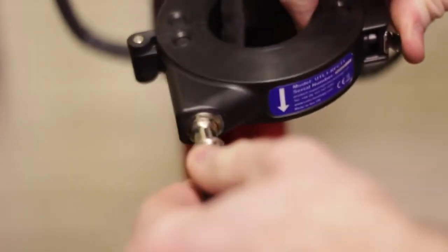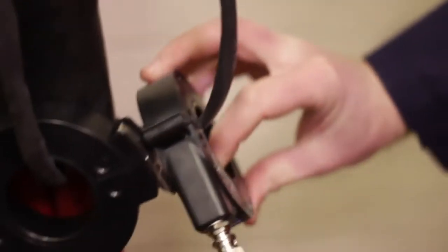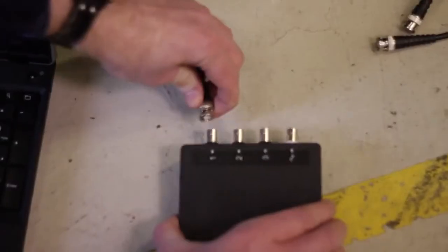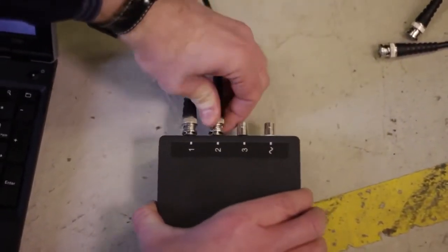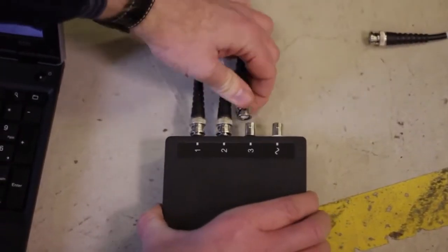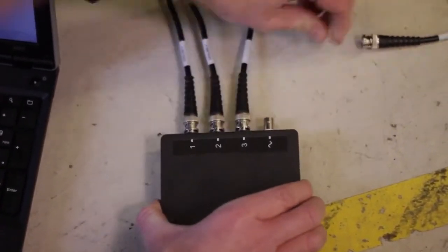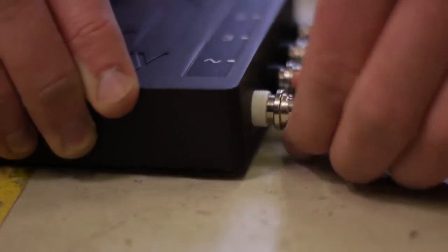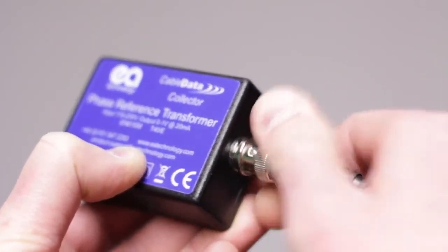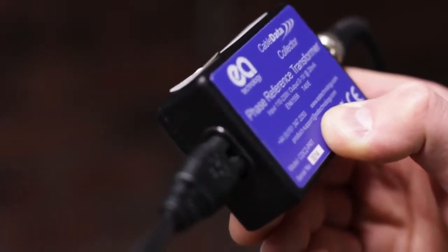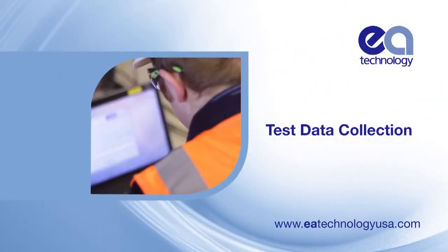Next, clip the RFCTs around the ground straps of the cable you are testing, one for each phase, and connect them to the collector unit. Now, connect the RFCT cables to the collector unit, one for each phase. Then connect the phase reference transformer via port 4 to a main supply to obtain a reference. That's the hardware part done. Easy.